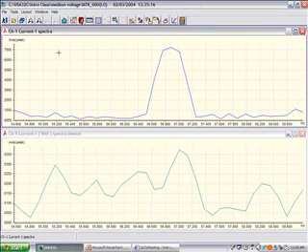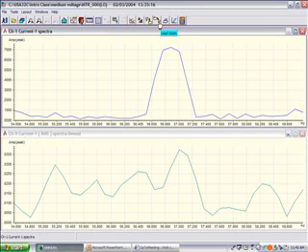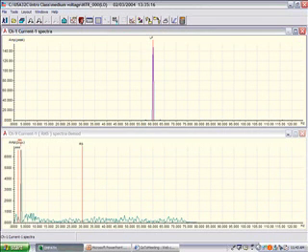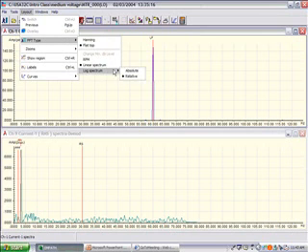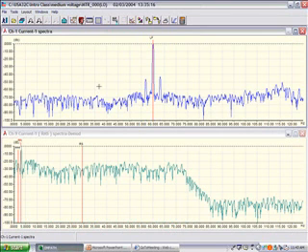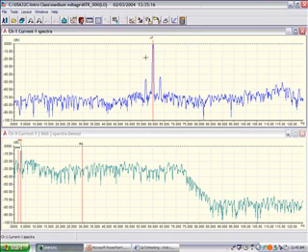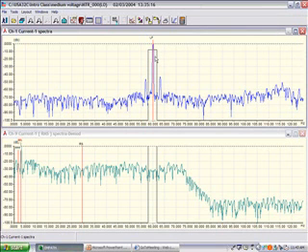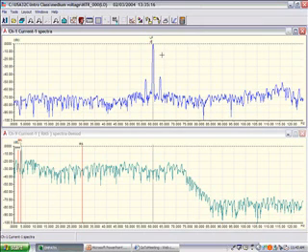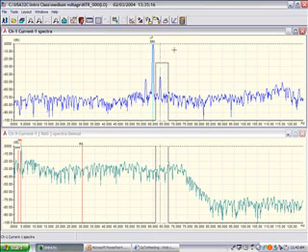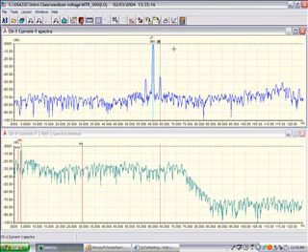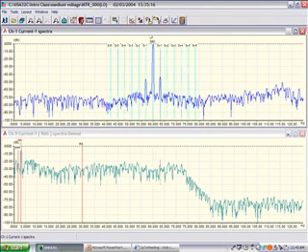So, for instance, the sideband that was showing at about minus 45 dB down is now showing at 0.7 amps as compared to 140 amps. It doesn't seem like a lot, but what is the relative magnitude of force? The relative magnitude is about 45 dB down. So, if I take a look at this.